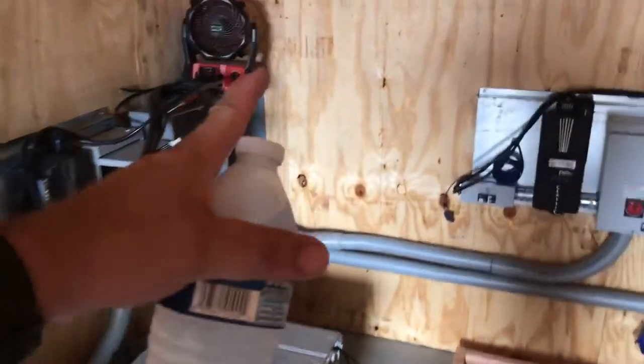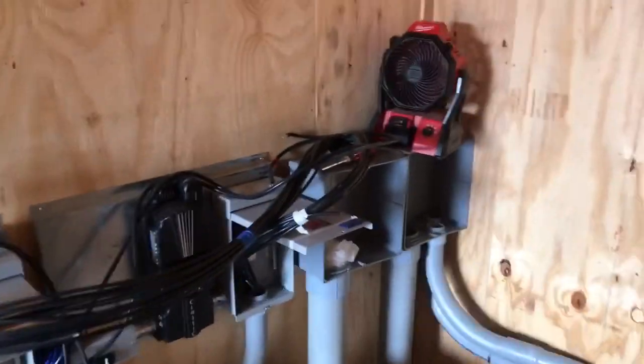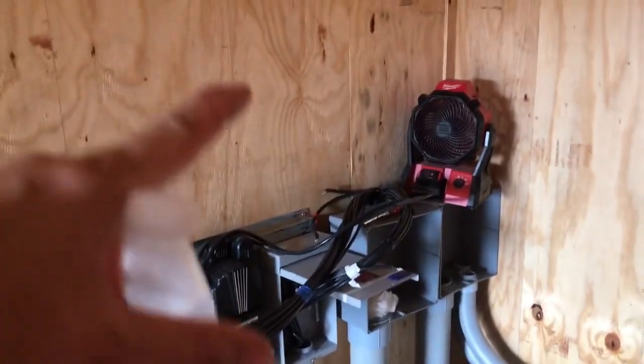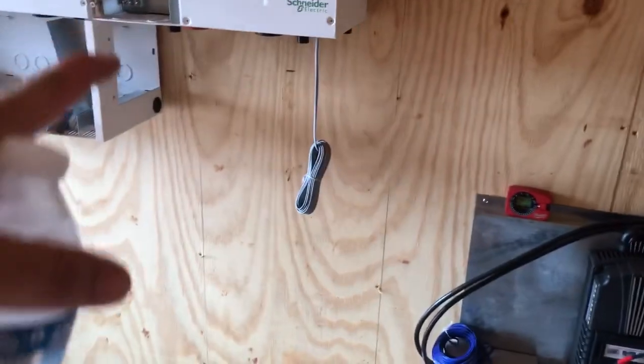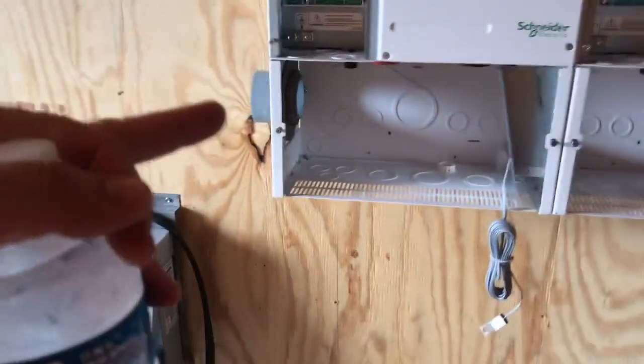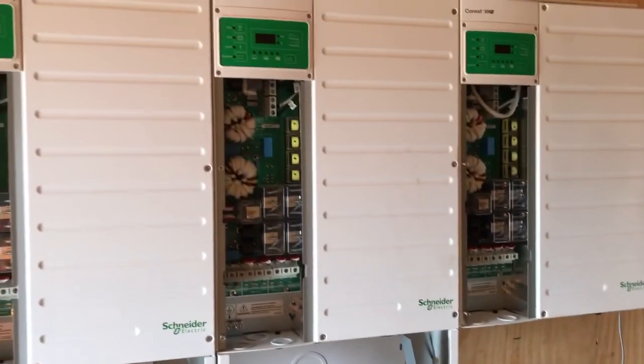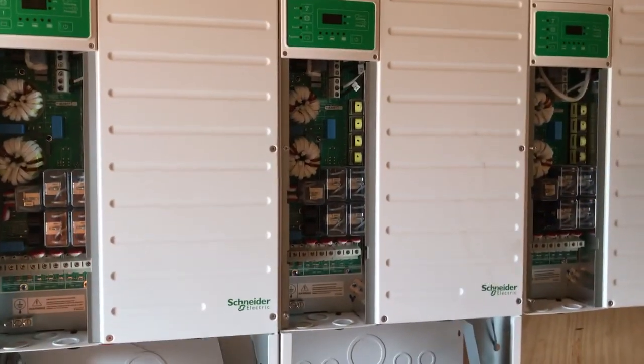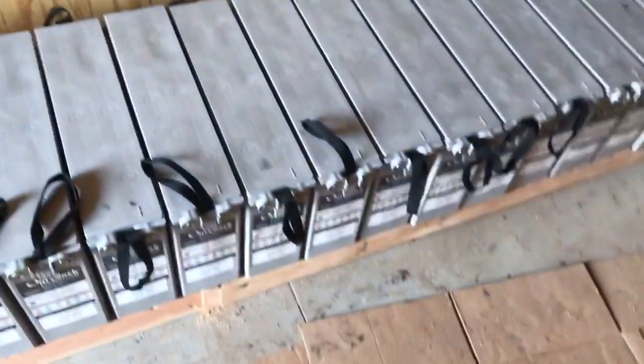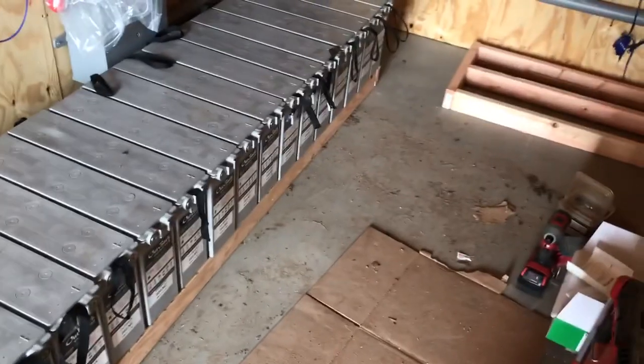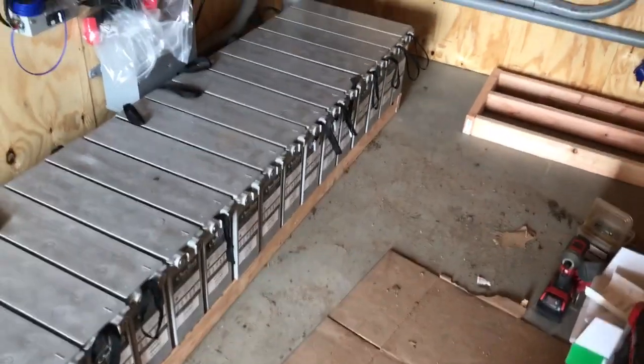AC service panel over here for input from the generator, and that's going to go into 2.5-inch conduit into the conduit box here when that gets set. Then this will come out right here for the power from the inverters to go into the house. This is 3 of the Conext XW6848s, and that'll tie into the battery bank. We'll put all these in series to make these 48-volt banks out through here.